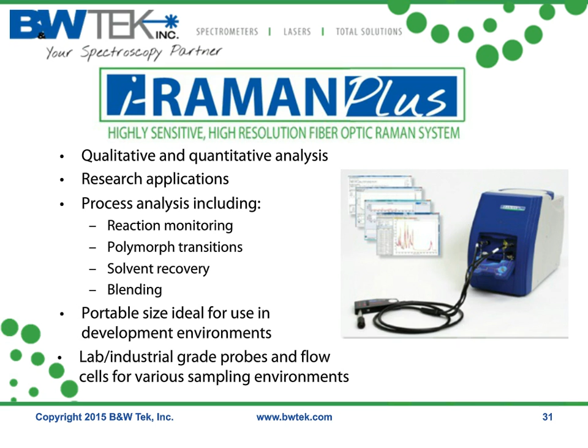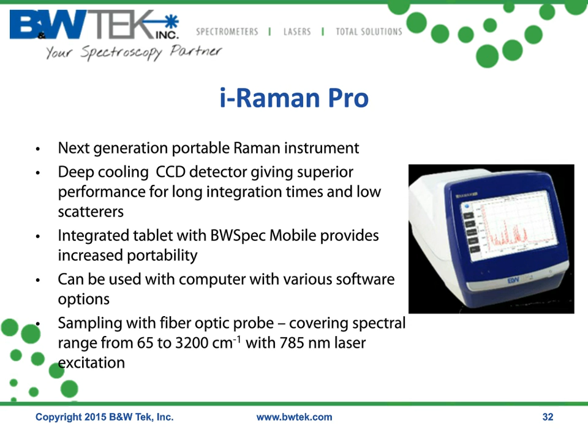Our next generation of instrument, the Raman Pro, brings even greater benefits in having deeper cooling CCD detectors, which give superior performance for long integration times and low Raman scattering materials. In this instrument, we have now an integrated tablet PC with our BW Spec Mobile. So you have even increased portability with this because you don't need to also port a computer with you. With this as well, we have various softwares that can be used with it, with a computer if that's the preference, and a sampling with the fiber optic probe covering the spectral range from 65 to 3200 wave numbers when using our 785 nanometer laser excitation for this system.